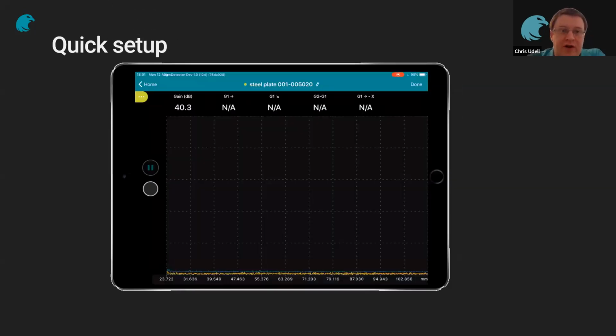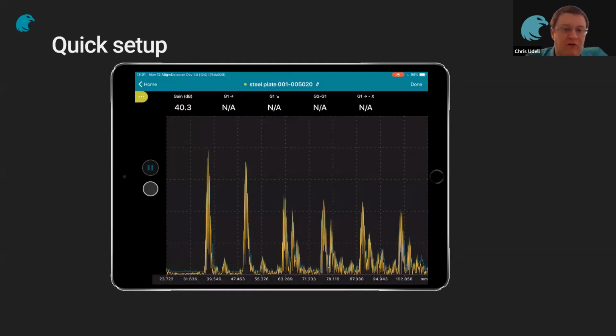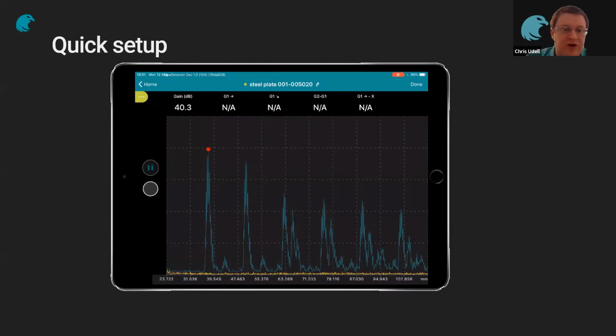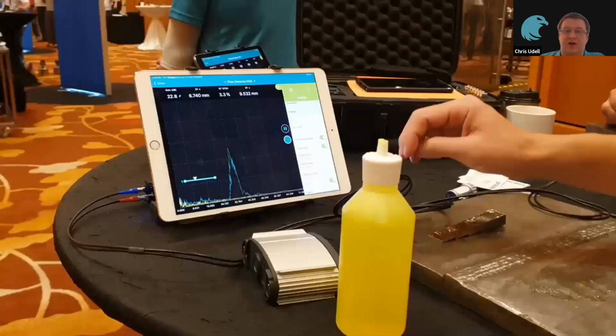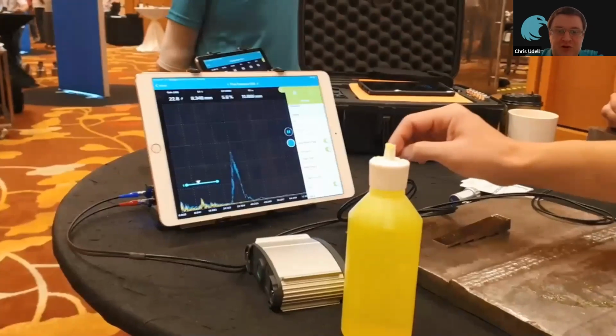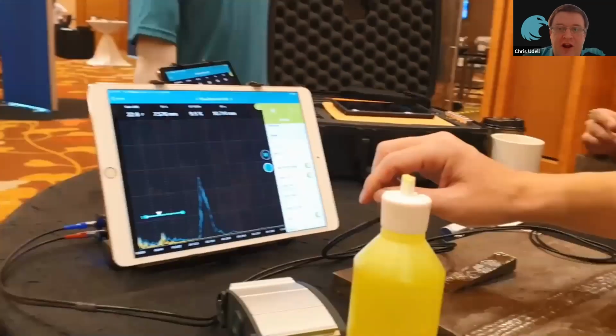Where the touchscreen is also very useful is on the setup as well. For example, if you're doing a DAC sensitivity calibration, what we can do is take the peak memory of the block, and then we just touch the peak on the screen, and then you've got your DAC in seconds. If you've made a correction, you just hit the red dot and redo it again. Or if you're recalibrating, you can correct the DAC very quickly. That's using a 0 degree on a back wall, but if you want to see it done in real life situations, here it is on an IIW block.